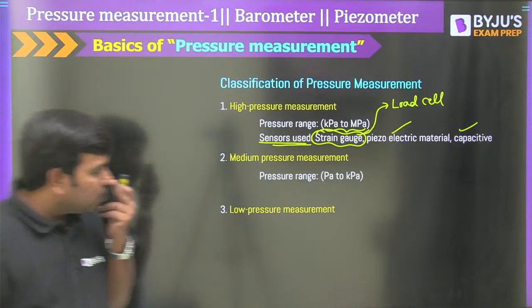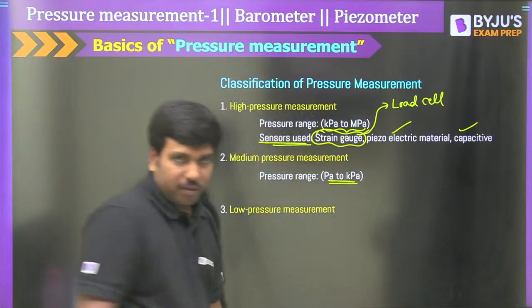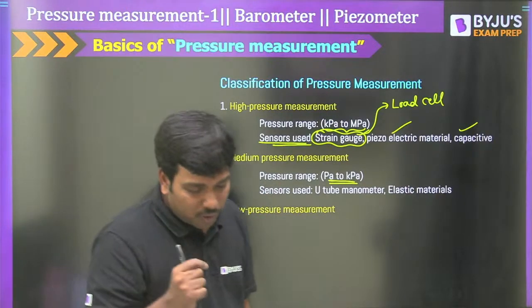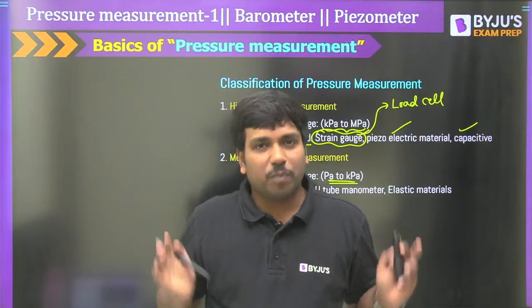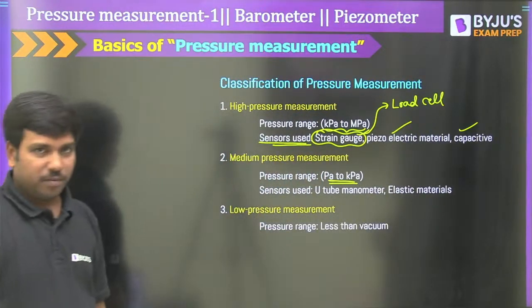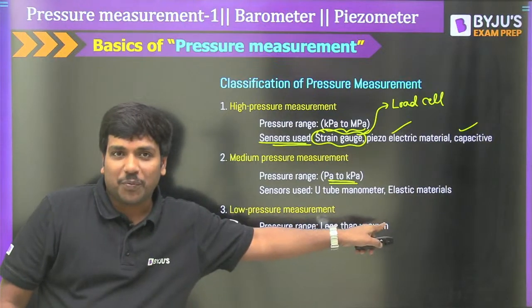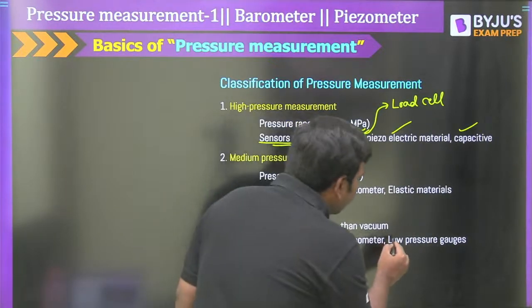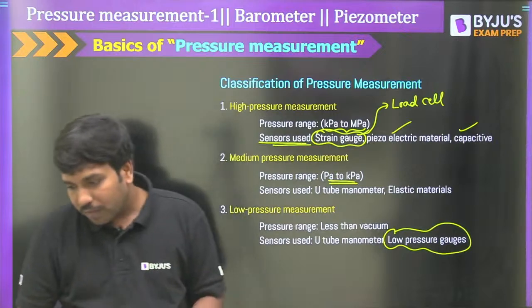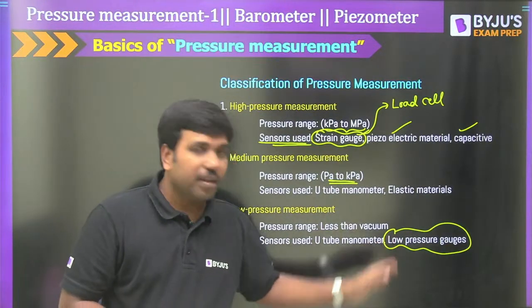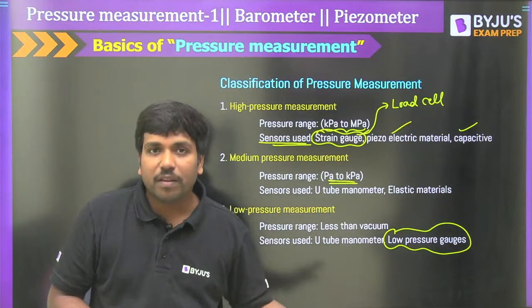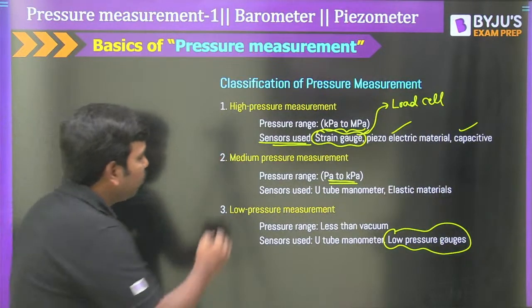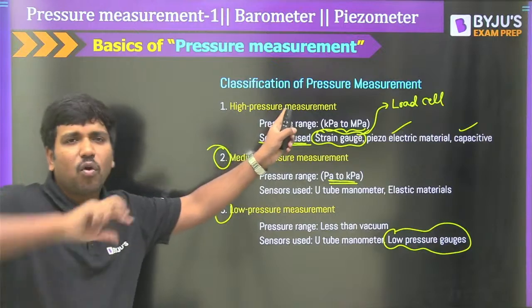Medium pressure measurement ranges from Pascal to kilopascal. Sensors used include U-tube manometer and elastic materials — specifically diaphragms, Bourdon tubes, and other special devices. Low pressure measurement covers even sub-vacuum pressures. Sensors for low pressure include U-tube manometer and low pressure gauges such as thermocouple gauge, Pirani gauge, McLeod gauge, Knudsen gauge, and ionization gauges.